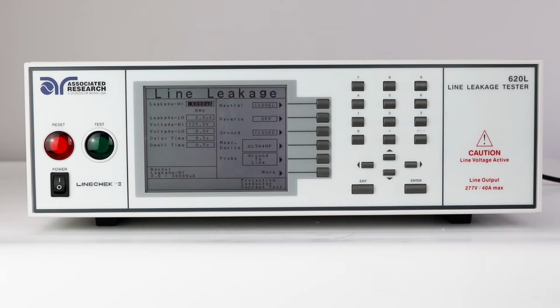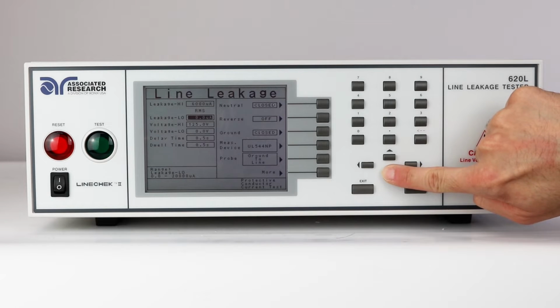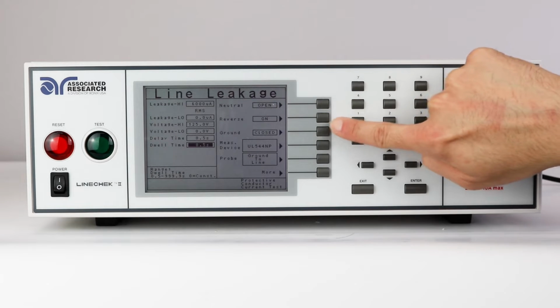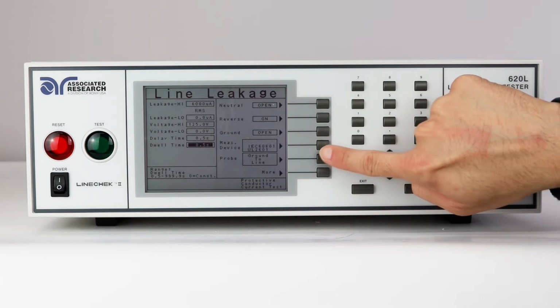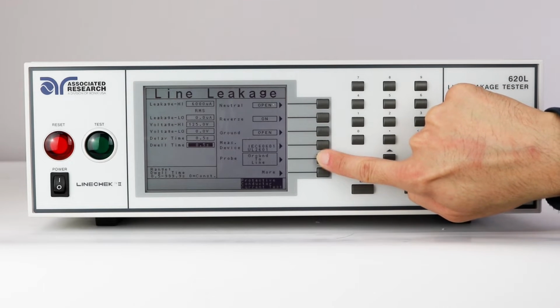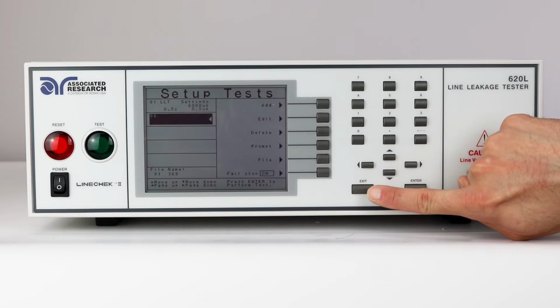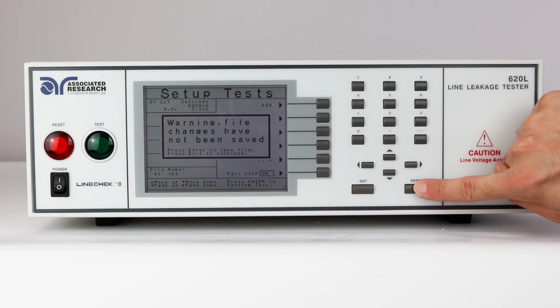For this video demonstration, we'll set up 2 line leakage tests. On the line leakage parameters screen, edit the parameters by using the arrow keys and the alphanumeric keypad. Use the soft keys on the right side of the screen to program the fault conditions, set the measuring device, and the probe configuration. Please refer to your appropriate safety standard to determine which conditions apply to testing on your products. Once you are done editing the test parameters, press the Exit key and a message will be displayed on the screen to save the changes. Press Enter to save the changes.